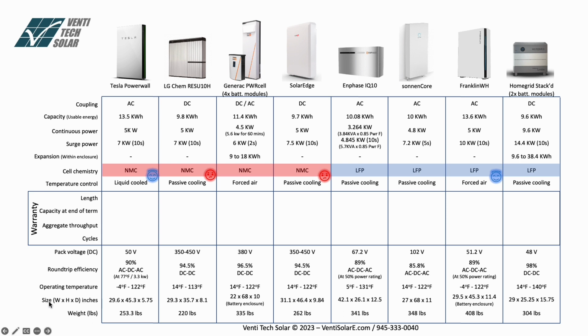On the size, I just wanted to point out that with NMC, the battery cells are smaller. For example, the thickness, 5.7 inches of dimensional depth compared to 8.1, 10, 9. So these are smaller in comparison to the LFP, which are 12 inches thick, 11, and 15. So there is a visible difference in size between the LFP and NMC cells. The 42 by 26 by 12 is much bigger than 29 by 45 by 5 something.